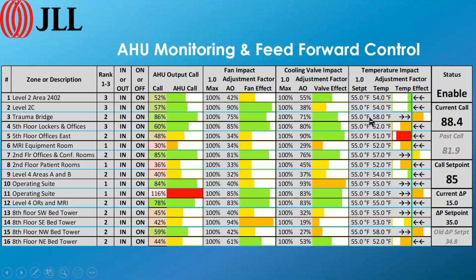And that's the point where I would start to think about raising chill water temperature up, and then continue to reset it up, so that I can get the valves to open back up. Once we get to a point where the valves are opening up, that's as far as I'd reset it. No point in having water flow out of the plant if you don't need to.